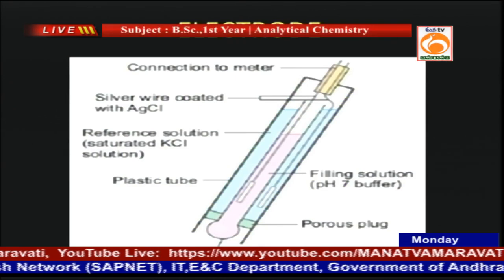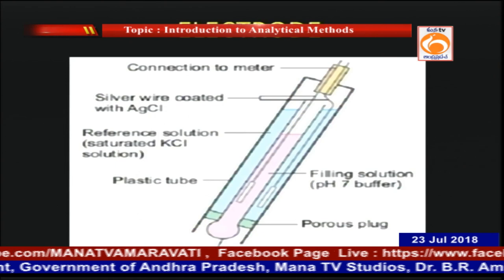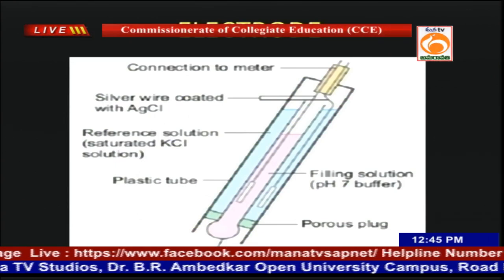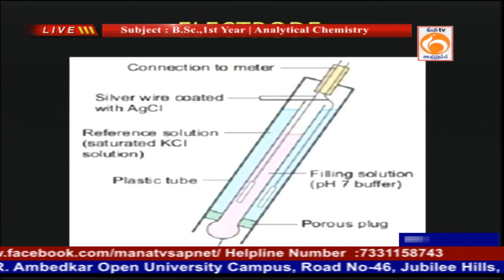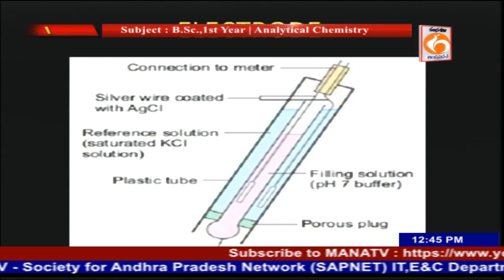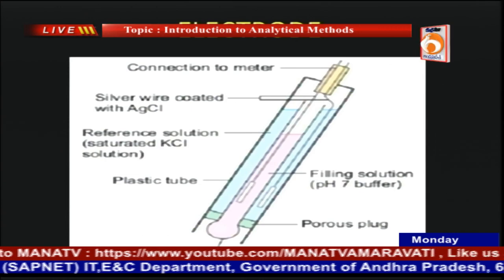to correct it back. Here, you have two electrodes, one reference electrode and one glass electrode. Nowadays, the two electrodes come combined in a single system, so what you are trying to measure here, I will tell you. You can see the glass bulb at the bottom, which is getting in contact with the effluent which you are trying to analyze. Here, that is a pH sensitive glass membrane. So the structure, how it is constructed, what sort of solution is filled, everything is available with you.